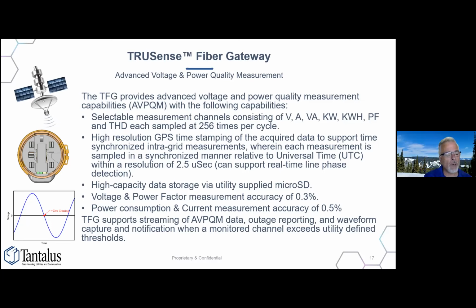There's also a feature in here called capture and notification. As I mentioned, you can set a rule around any one of these measures, and you can set a threshold. So you can set a maximum value and a minimum value. The system will monitor it 256 times per cycle, and if the measured value goes outside of the range that you have set for a period of time that you have also defined, as small as 1 cycle and as long as, we haven't quite defined that yet, but it'll be a longer period.